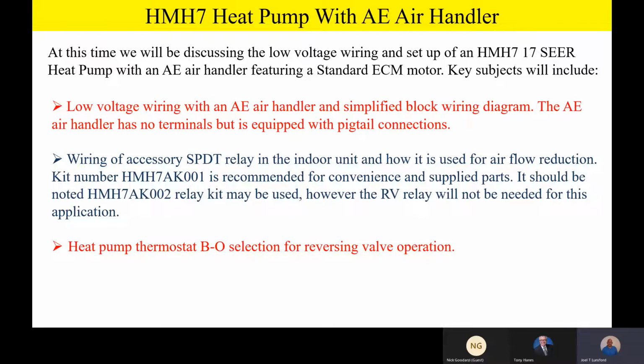In addition, if the contractor later on, or if the homeowner later on wants to convert it to a heat pump, you've already got that bi-flow filter dryer in the refrigeration circuit, and you don't have to open the circuit back up to replace it with a bi-flow dryer. So we always recommend a bi-flow filter dryer, and then the relay kit, as we talked about, because of convenience and supplied parts. Finally, we want to make sure our heat pump thermostat has a BO selection, because that B is going to be energized for the reversing valve in the heating mode.